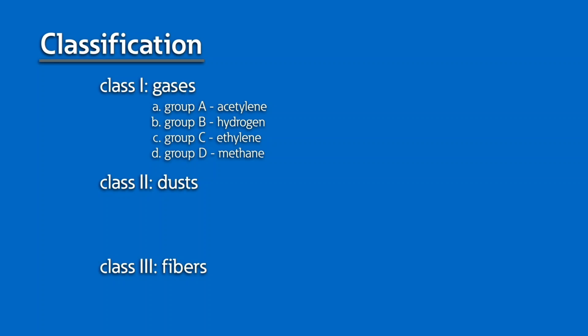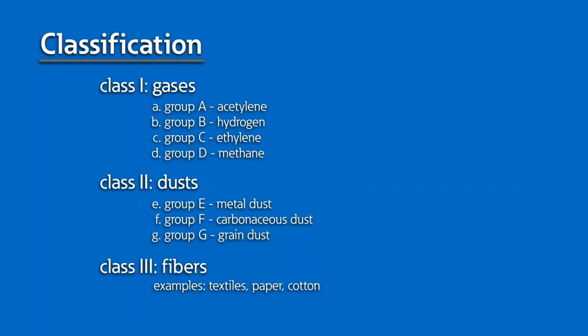Class 2 atmospheric hazard is reserved for combustible dust, which is grouped based on combustion characteristic. Group E is for metallics such as aluminum. Group F covers carbonaceous dust like coal or coke. Group G is organic elements, sugar and starch, for example. Class 3 covers locations where combustible fibers or flyings are present. Some examples include industries that work with textiles, paper, or cotton.